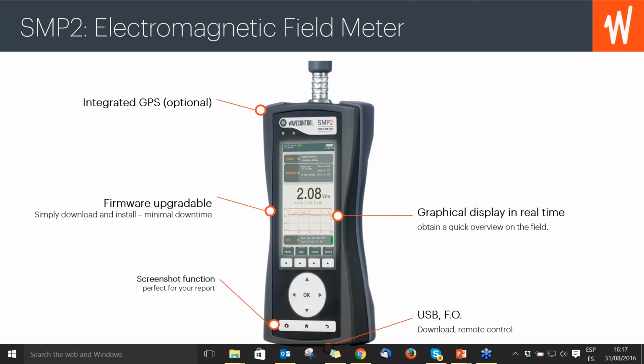The SMP2 can be connected to software that we provide with it through USB cable. This USB cable is mainly for downloading the measurements, but also it can be connected through fiber optics, which is mainly for remote controlling the unit, because the presence of a human body next to the equipment may interfere in the measurements because of the physics laws, and then many standards suggest to use a fiber optic connection to remote control the equipment and make the measurement by distance.